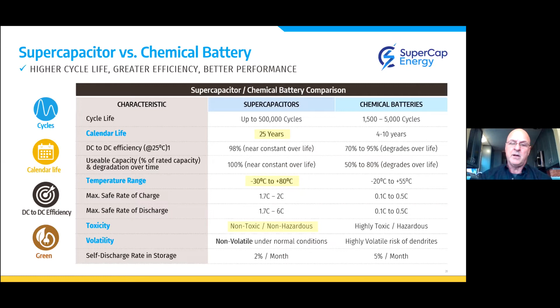Supercapacitors, because of their long life and ability to cycle daily without degradation, provide the lowest life cycle cost. Life cycle cost is the total money spent over the analysis period divided by the total energy delivered, in kilowatt hours, so it's dollars per kilowatt hour. VRLA valve regulated lead acid batteries, typical in telecom, have a replacement cycle of about 5 years. Lithium can go 7 to 10 years, and supercapacitors 25 or more years. That takes the levelized cost of energy down to about 8 cents a kilowatt hour in this example.